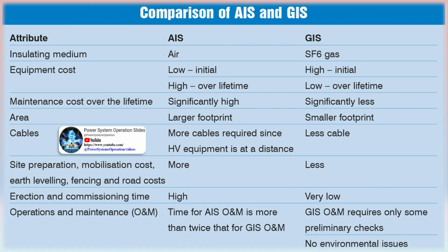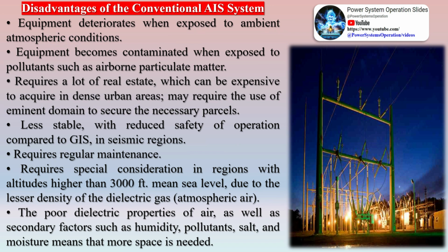Disadvantages of the conventional AIS system: equipment deteriorates when exposed to ambient atmospheric conditions. Equipment becomes contaminated when exposed to pollutants such as airborne particulate matter. Requires a lot of real estate, which can be expensive to acquire in dense urban areas, and may require the use of eminent domain to secure the necessary parcels. Less stable, with reduced safety of operation compared to GIS, in seismic regions.